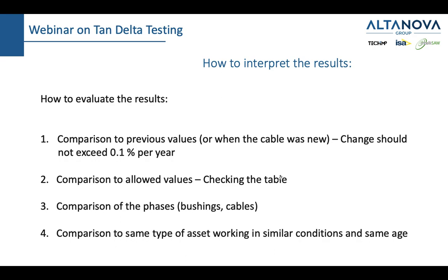How do we evaluate results? So first, as we said, we compare to the previous values. This is the best way to assess your tan delta value or your power factor value, because your transformer, when it came from the factory, was probably tested for tan delta in the factory. So you do have that information somewhere. If you can dig out that information and bring it to the test site, you will see what the tan delta was when the transformer was produced and what it is today, which can definitely tell you if you have an issue or not. Also, as we mentioned before, the change should not exceed 0.1% per year or less.